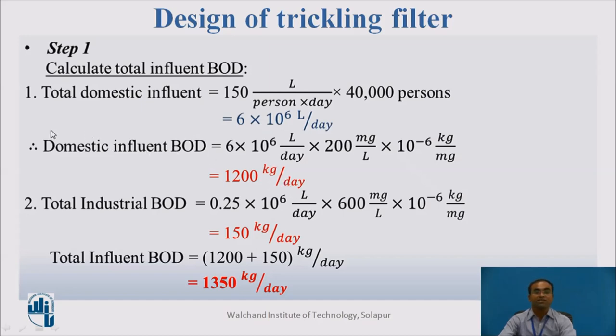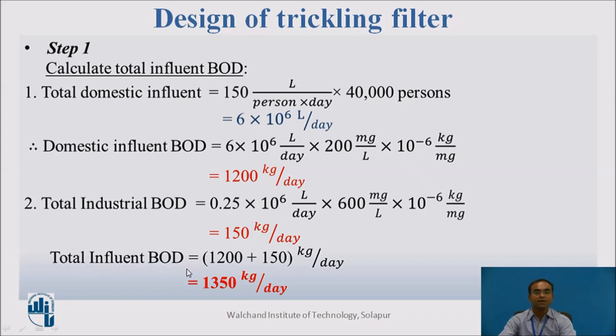The total BOD from domestic influent is 1,200 kg/day. For industrial BOD: 0.25 × 10⁶ liters/day × 600 mg/L × 10⁻⁶ kg/mg = 150 kg/day. Therefore, the total influent BOD is 1,200 + 150 = 1,350 kg per day.